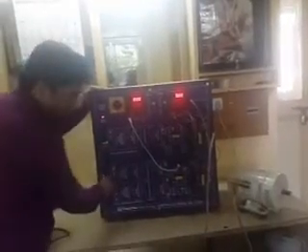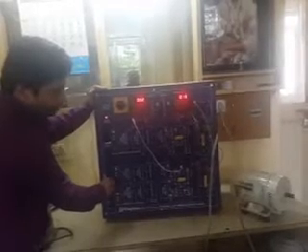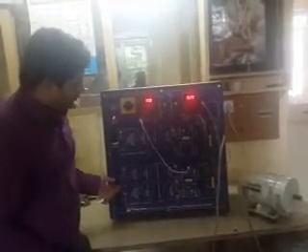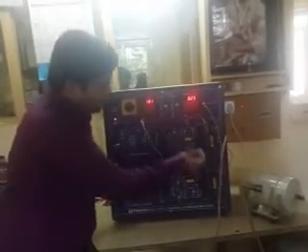I will show you the demonstration. I will increase the firing pulse of the SCR to increase the resultant DC voltage. As you can see, when I am increasing the firing pulse, the DC voltage is increasing. With this increase, the motor is gaining speed.